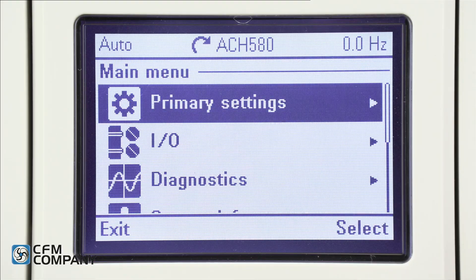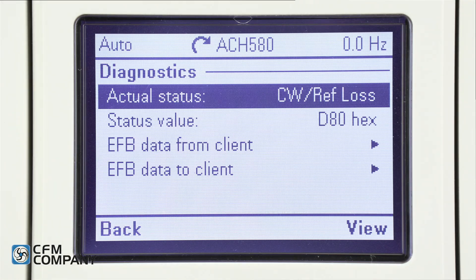Not covered in this video, the ACH 580 does have a diagnostics menu. Press menu, arrow down to diagnostics, press select, arrow down to communication status, press select, then select embedded field bus (EFB). The diagnostic screens can help to confirm proper communication with the building automation system and also to help troubleshoot communication issues.